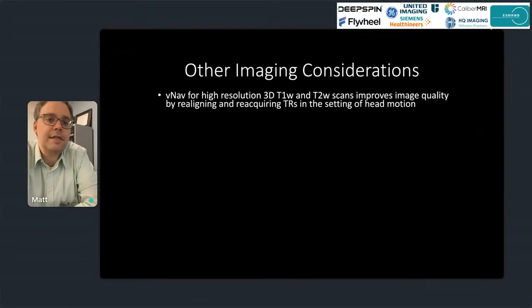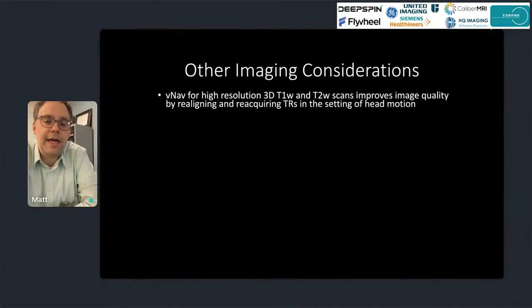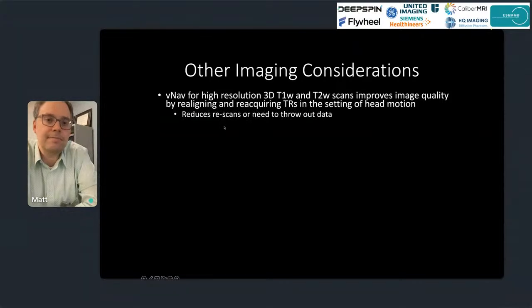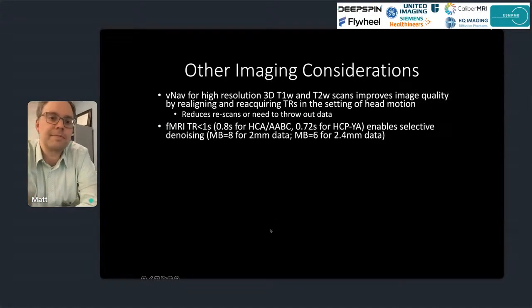For 3D high-resolution scans at 0.8 mm isotropic, it really helps to have internal motion correction. This can be done with an internal low-resolution EPI navigator called the VNAV. Basically, if the person moves their head, it will realign the k-space data and reacquire any data that was corrupted by head motion. So even with some motion during long scans, you can still get high-quality scans, reducing the need to repeat scans or discard whole subjects due to poor-quality structural imaging.